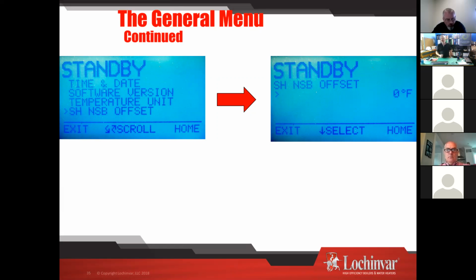So whatever you set in there for a temperature, a number of degrees right here. If I set that to 30 degrees, when I go into night setback, I'm going to deduct 30 degrees from my targeted water temperature, including wherever I am for outdoor reset. Residentially, probably not a solid idea to use that one. This is more for a light commercial type of scenario. I might want to use that there.